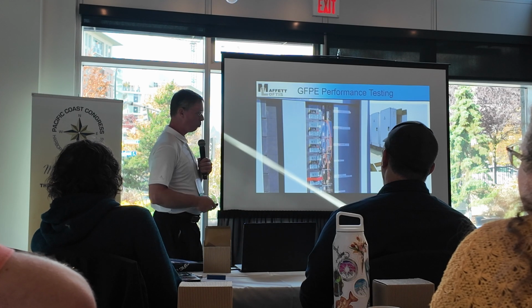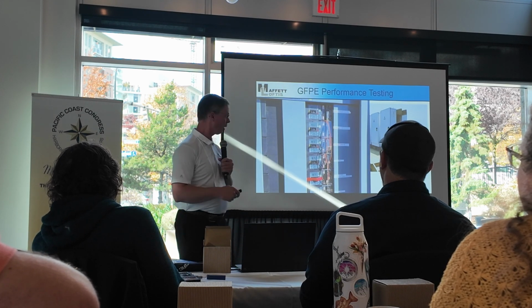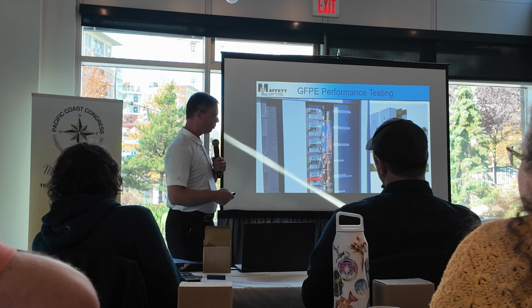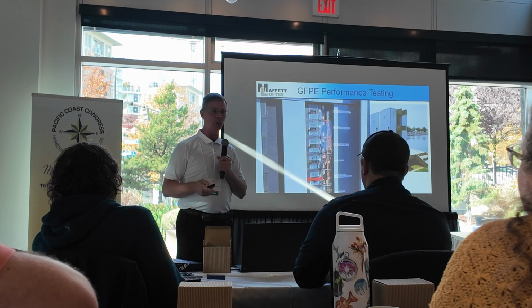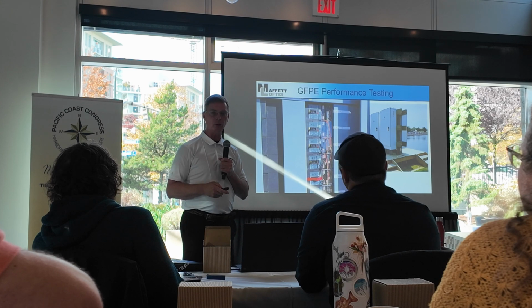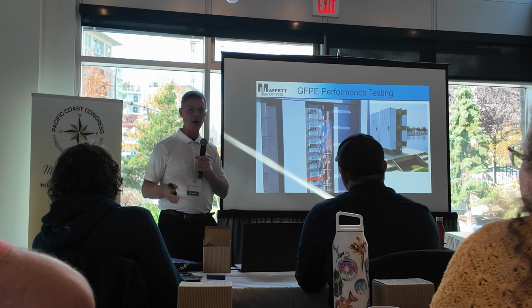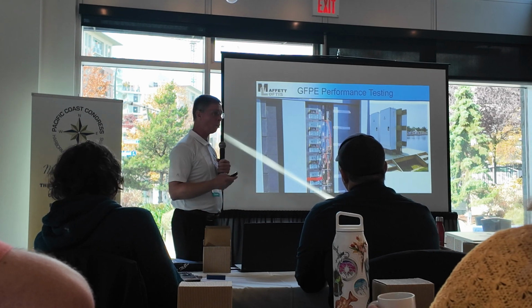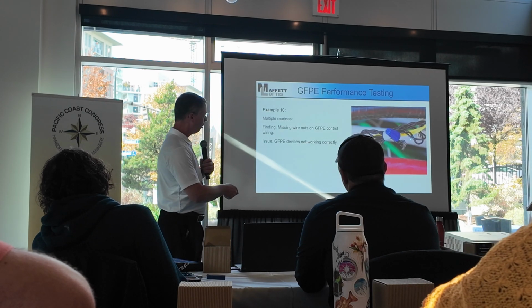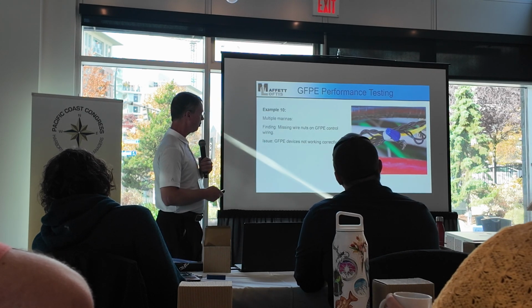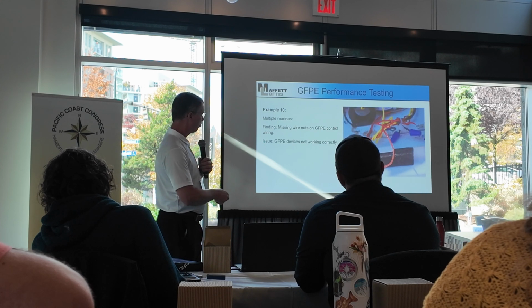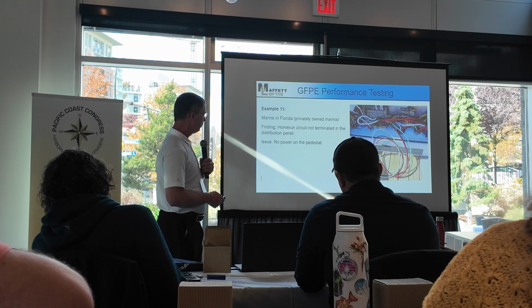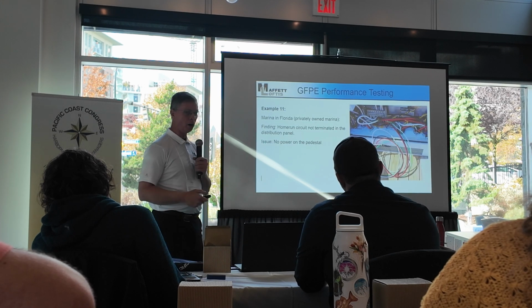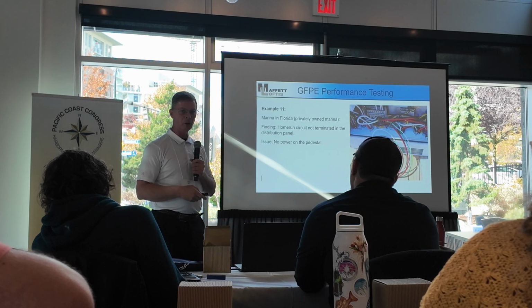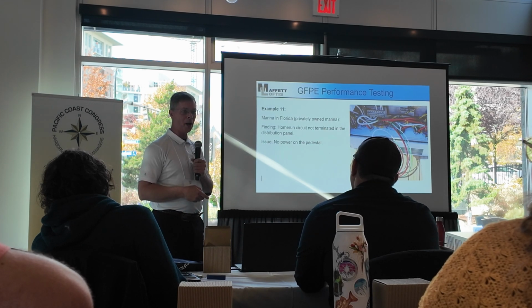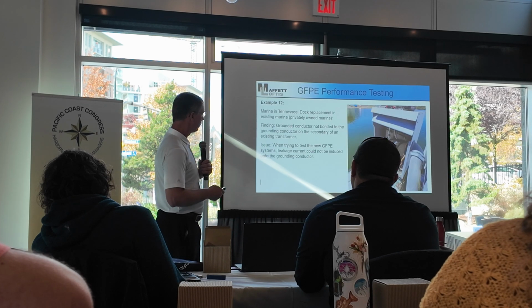Here, the GFE system was tripping the main breaker. This actually is the service equipment here, and it was tripping the main breaker, so they just disabled the GFE system because it's such a nuisance. Because it kept tripping the entire marina out every time it tripped something. So the coordination is a very important piece. I find wire nuts off of control wires. There's another one off. Here's a wire that's completely off. We found one circuit not even wired. They said it's all done. Try to power up something and, this one's not powered, and start pulling that wire, and there it is.